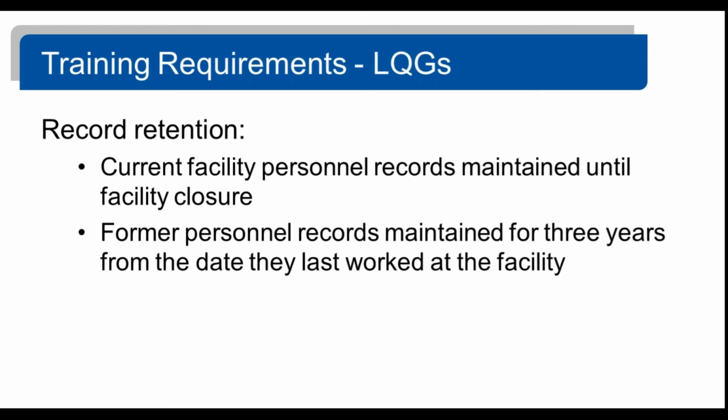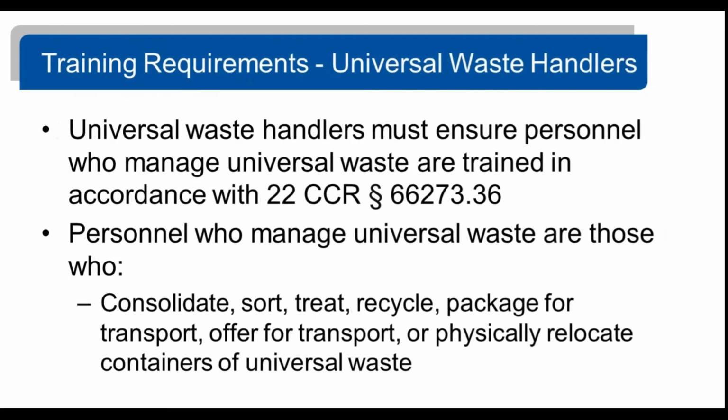Now, for any former employees who received training, the documentation must be maintained for at least 3 years from the date they last worked at the facility. So for large quantity generators, training requirements are spelled out in state regulations, much more defined than those requirements for employees who work at small quantity generator facilities.